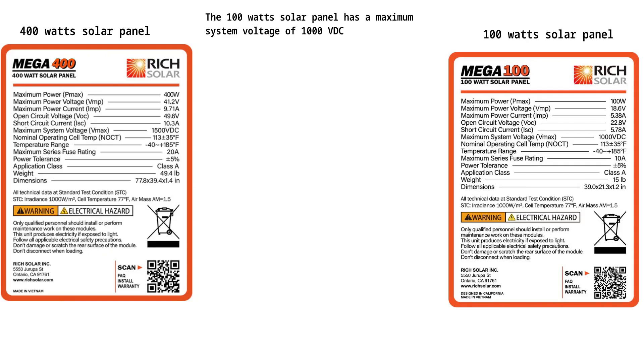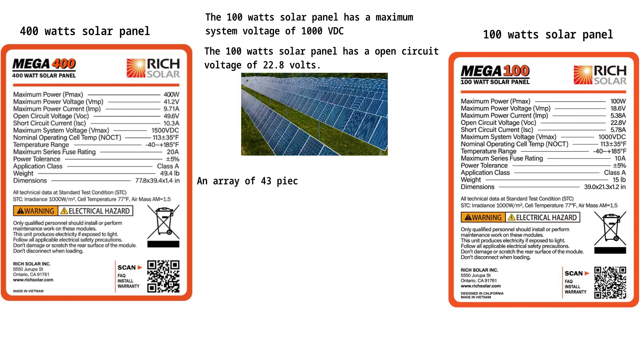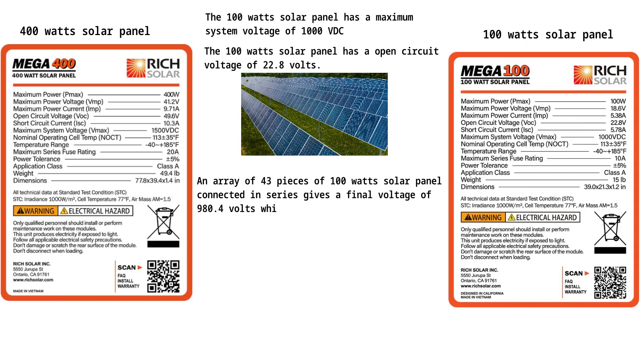This means that while connecting 100-watt solar panels in series to generate higher voltage, the total voltage should not exceed 1000 V. The 100-watt solar panel has an open-circuit voltage of 22.8 V. An array of 43 pieces connected in series gives a final voltage of 980.4 V, which is close to the 1000 V limit. So when connecting 100-watt panels in series, you should not exceed 43 pieces in a single array.